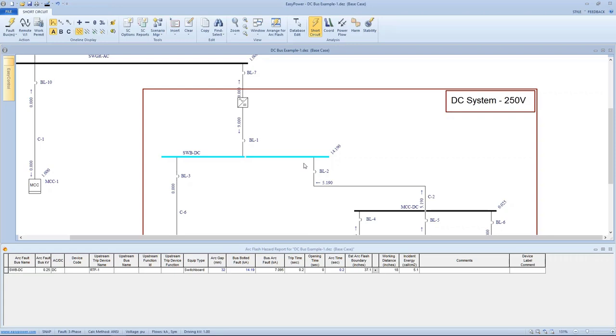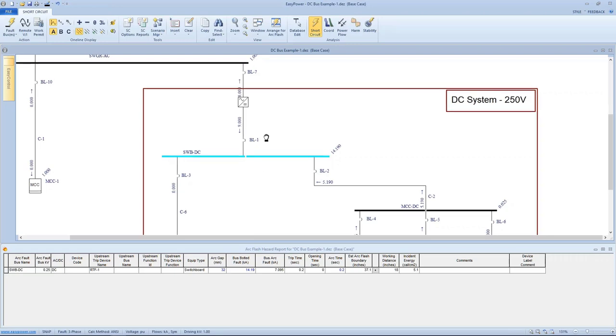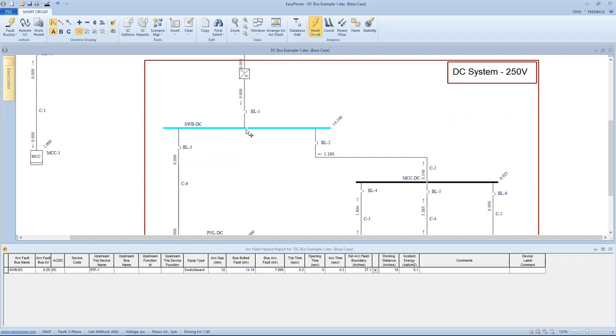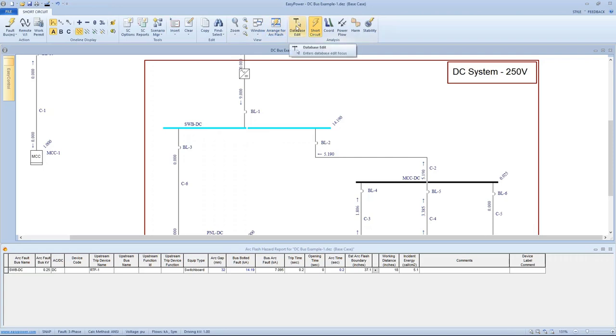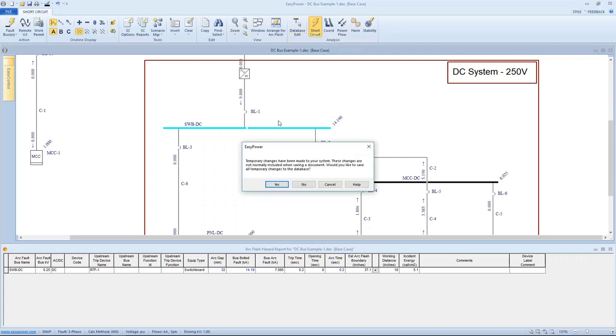Now, that's not necessarily the final answer, but that's one of the constraints we have when we look at hybrid systems, especially in the low voltage area. And it's encumbered by the fact that we have relatively high operating currents in the DC system and the fault currents for an arcing fault in the DC system aren't excessively high compared to those load currents. Again, we'll touch on that more in a couple weeks when we talk more about the low voltage arcing protection and arc modeling.